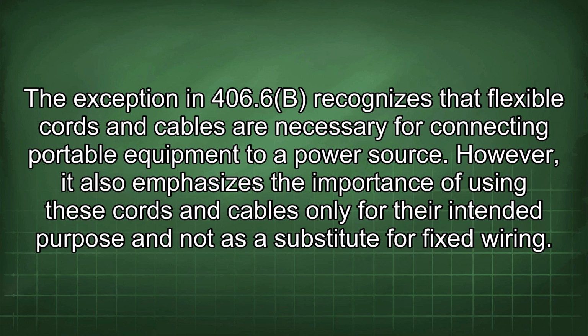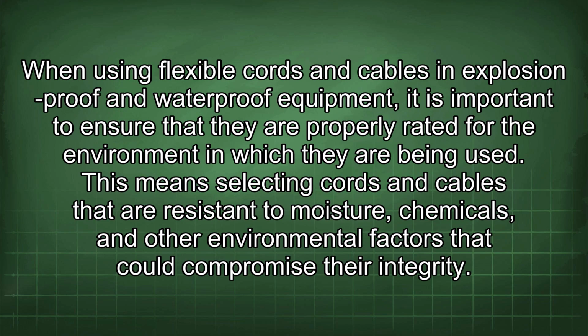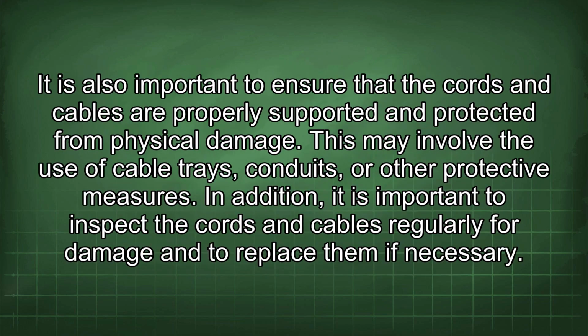The exception in 406.6(B) recognizes that flexible cords and cables are necessary for connecting portable equipment to a power source. However, it also emphasizes the importance of using these cords and cables only for their intended purpose and not as a substitute for fixed wiring. When using flexible cords and cables in explosion-proof and waterproof equipment, it is important to ensure that they are properly rated for the environment in which they are being used. This means selecting cords and cables that are resistant to moisture, chemicals, and other environmental factors that could compromise their integrity. It is also important to ensure that the cords and cables are properly supported and protected from physical damage. This may involve the use of cable trays, conduits, or other protective measures.